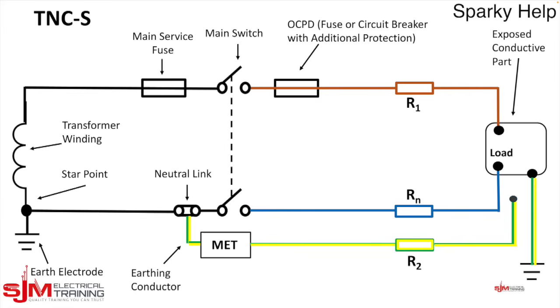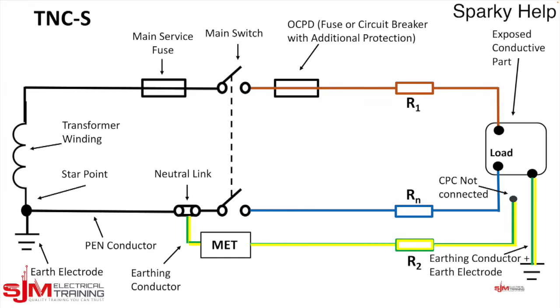and like I say, in this case then the armoured, you wouldn't terminate it as normal. You'd either terminate it into a plastic box or maybe into a compression gland but not continue the earth through. So there's no point running an extra core in the earth in the armoured cable if that's what you're going to do. So the armouring would be perfectly sufficient in most cases anyway. And like I say, the important part, not to connect as per the regulations. And we put another earthing conductor in, so again, because the earthing conductor may well be buried, this could end up being a 16 mil size pure and simply because you've buried it. But at least you're not running the distance back to the existing installation.